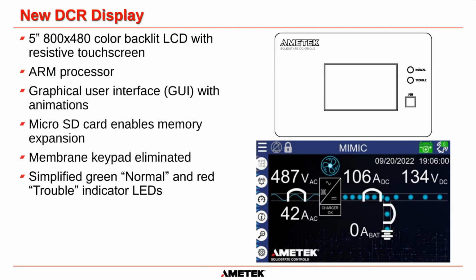So here, this is our new DCR display. It's a 5-inch, 480 or 800 by 480 pixel color backlit LCD with a resistive touchscreen. It uses a modern ARM processor to do all the computations. We have a brand new graphical user interface that enables animations and makes navigation much easier. We have a micro SD card that enables memory expansion, so we can record things like the battery history log. We got rid of the membrane keypad because with the touchscreen we don't really need it to navigate, and it is difficult to use. And we eliminated a lot of the LED indicators on the front panel and just put a normal or trouble alarm. So the normal would be green if everything is operating as expected, and the red trouble indicator LED will be on if there's any problems.